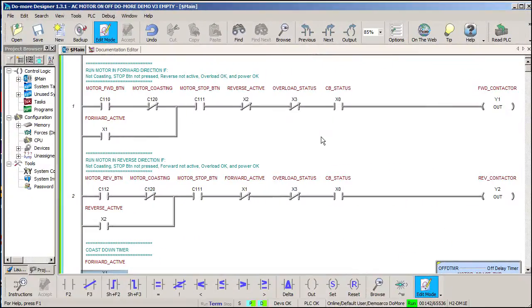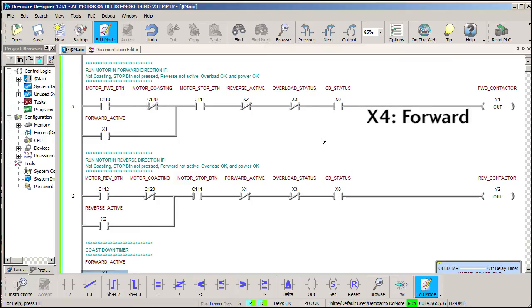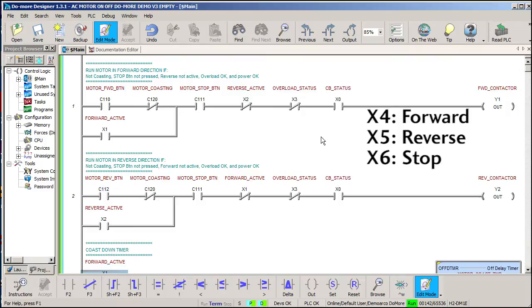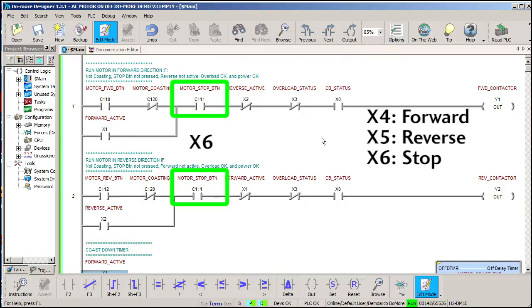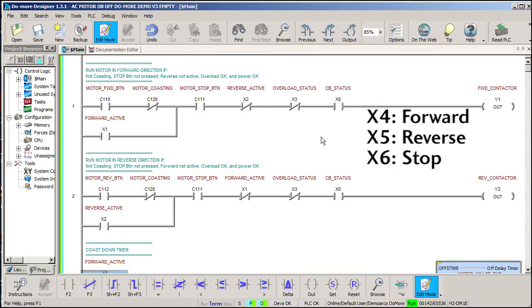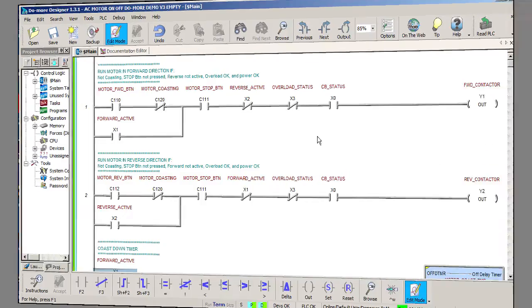Changing all of this over to a system that uses mechanical buttons instead of the virtual C-more HMI buttons we used here is easy. Let's assume the start button comes in on X4, reverse on X5, and stop on X6. Well, then you just replace these with X4, these with X5, and these with X6. Don't forget to make sure that the forward and reverse buttons are momentary normally open buttons and the stop button is a momentary normally closed button.